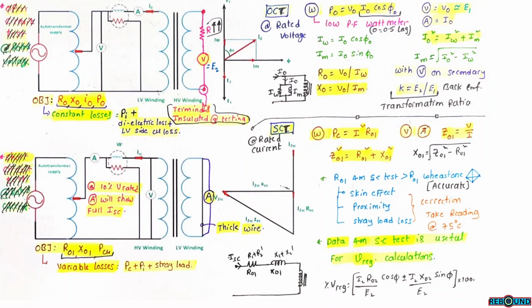Open circuit test and short circuit test. This is the circuit diagram for the open circuit test. The LV side is supplied and the HV side is kept open, or it may be connected through a high resistor and voltmeter. If we keep the transformer secondary or HV side open, then the terminals must be properly insulated during testing.